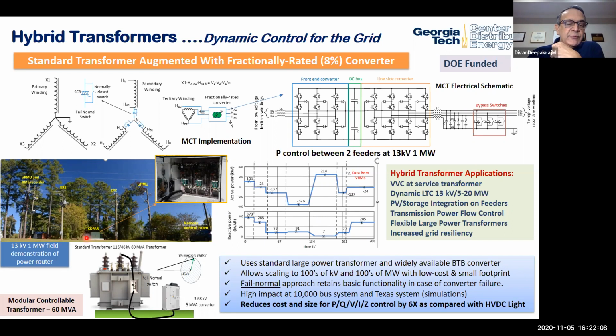At Georgia Tech, we built a 13 kV megawatt-scale device and interconnected two distribution feeders at 13 kV. We were able to show that we could transfer power at will between the two feeders. This was very interesting technology because it shows a way to work with existing utility assets, to stiffen and augment the systems they have, and get the power flow control functionality they need.